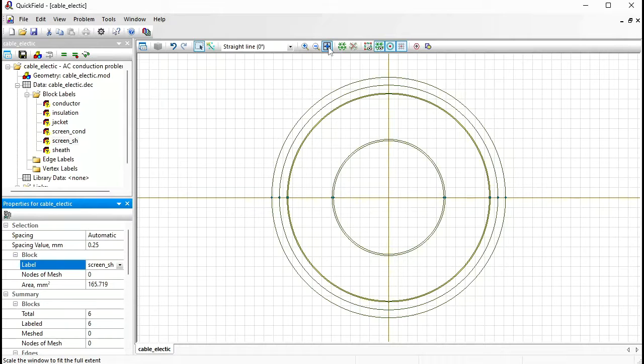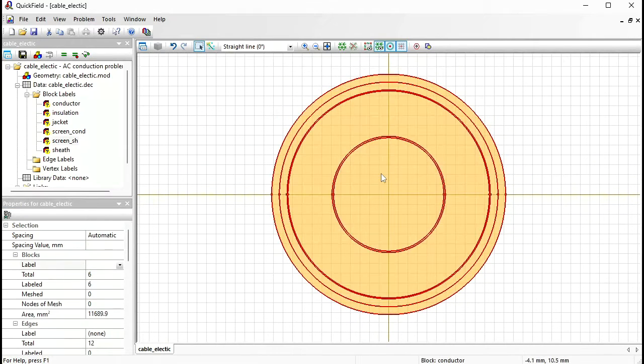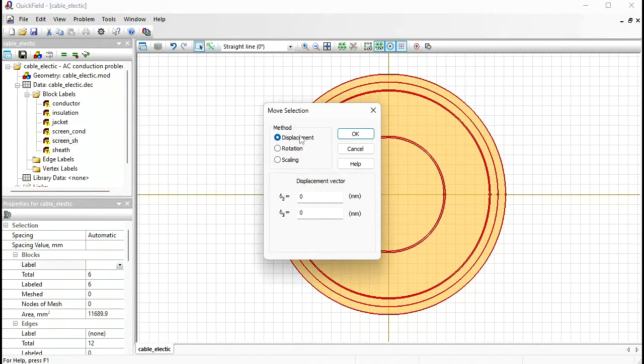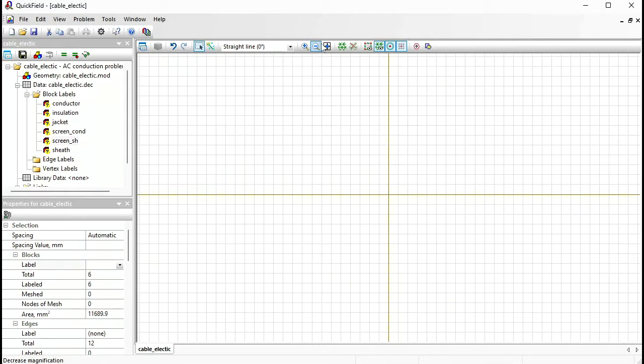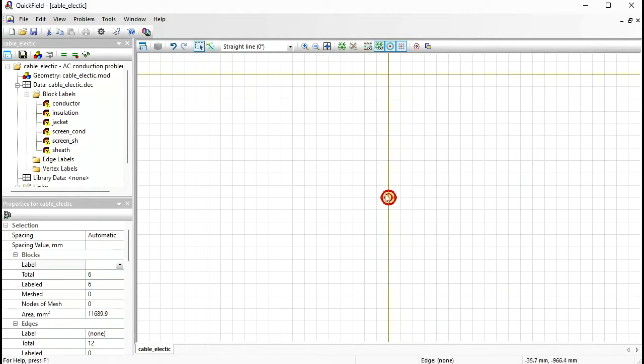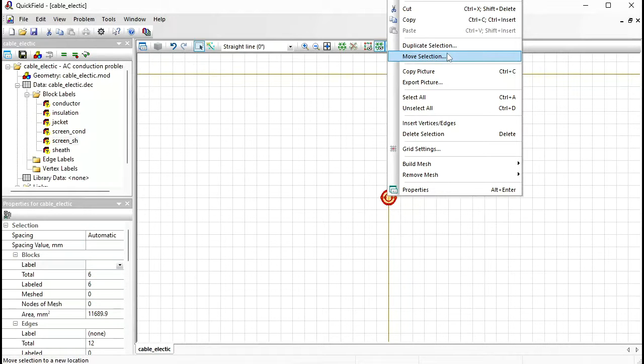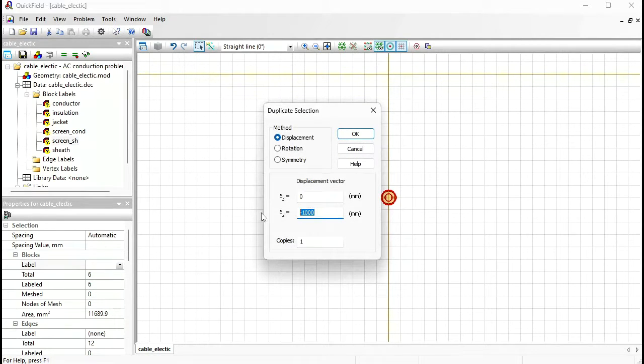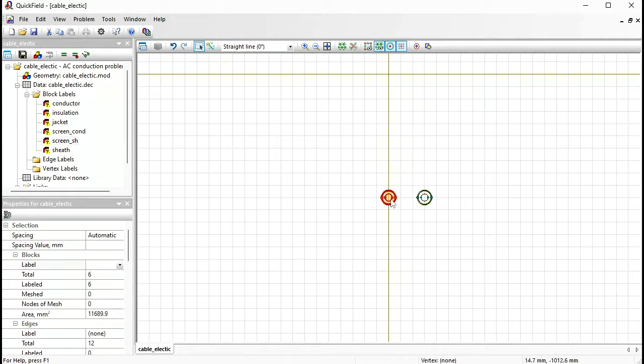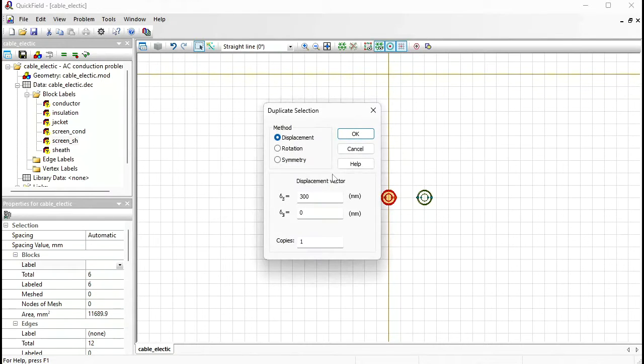Okay, the cables are buried at the depth of 1 meter, and the spacing between cable centers is 300 millimeters. So switch to select objects mode. Select the cable, right click, move selection, displacement by 1 meter down, and I need to copy this duplicate selection, 300 millimeters to the right, and again duplicate selection, 300 millimeters to the left.